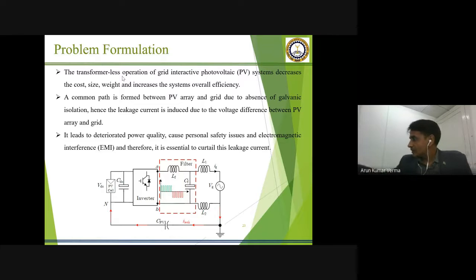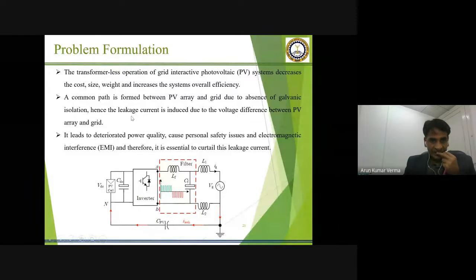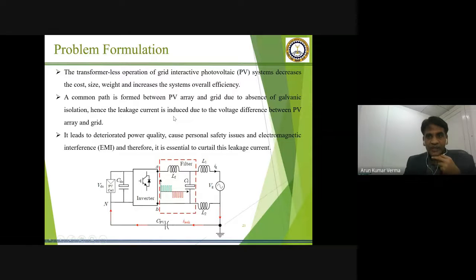Okay, so a common path is formed between a PV array and grid due to the absence of galvanic isolation. Hence, the leakage current is induced due to the voltage difference between PV array and grid. So the value of this leakage current must be less than 300 milliampere. If it is less than this, it is not dangerous. Otherwise, this leakage current is dangerous to the person who is working on the system. Okay.